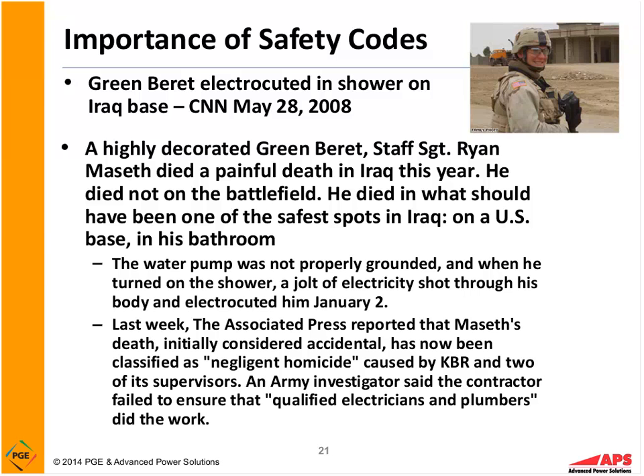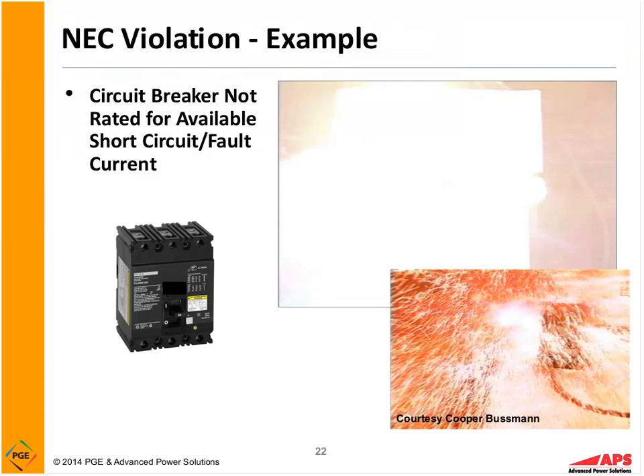So it's very important we follow safety codes to avoid things like this. We have NEC, National Electrical Code violations. Again, another violation is a circuit breaker may not be rated for the available short circuit or fault current. This occurs quite frequently. In the power system studies we do, looking at arc flash, a lot of times we have what's called underrated circuit breakers. So, breakers not rated for the total amount of current that could flow through them during a fault condition. And if that occurs, this is the potential outcome, where the breaker can actually explode or be significantly damaged, and again, not protect the personnel, in fact, cause significant exposure to hazards.